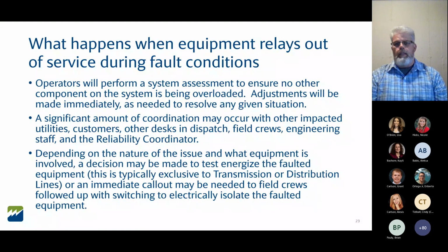being overloaded. If I have two transformers in parallel and one of the transformers trips, guess what? That load's still going to be served, but through the other transformer or maybe automatically through other transmission lines. So one of the first things we do as system operators is we perform an assessment on the system to make sure we're not overloading any other equipment. And again, if we do find an overload, then we're going to have to focus our attention on that.